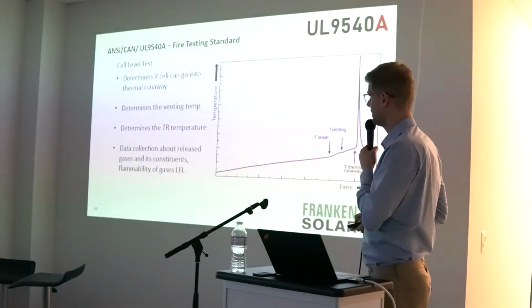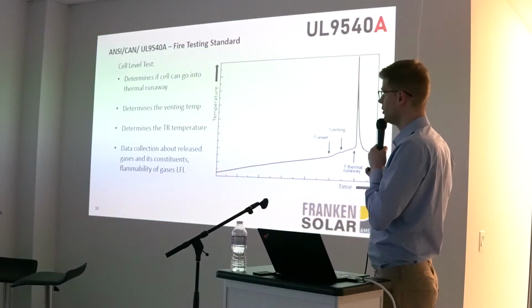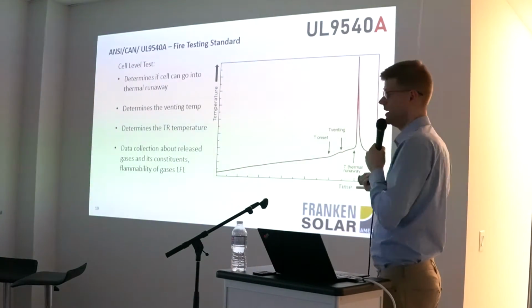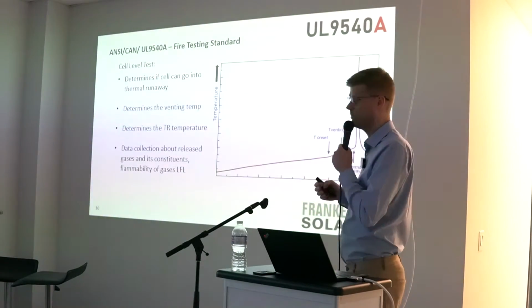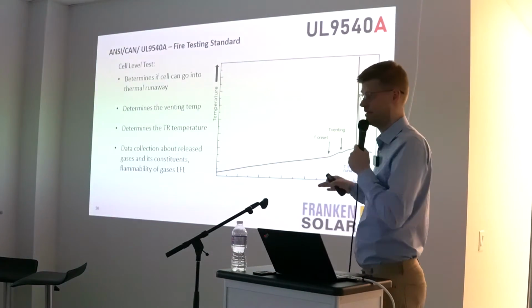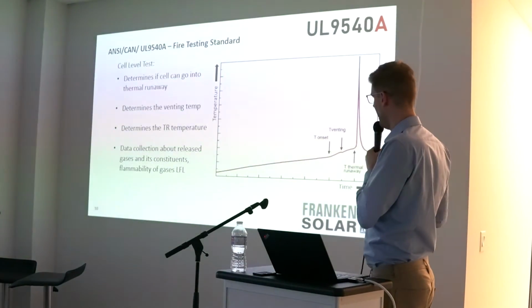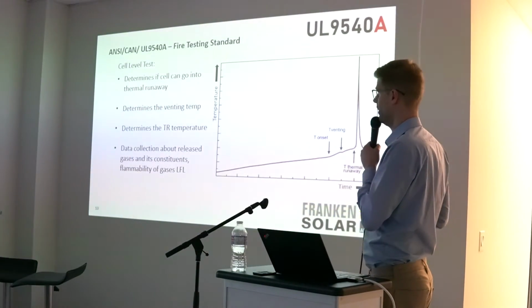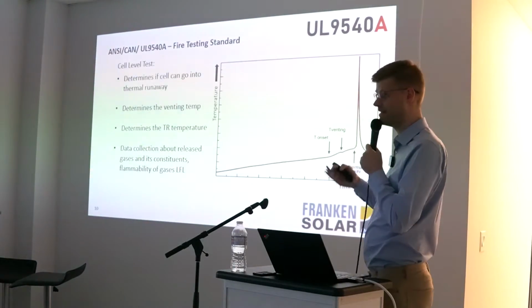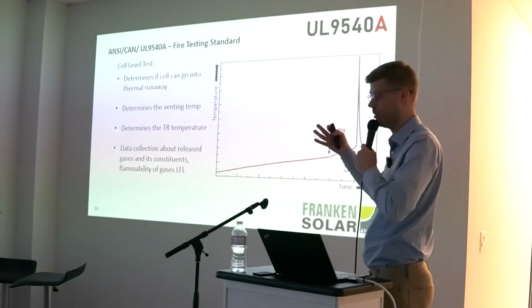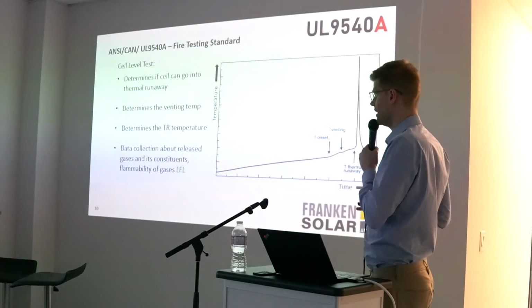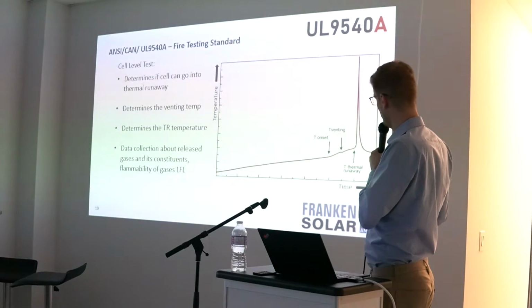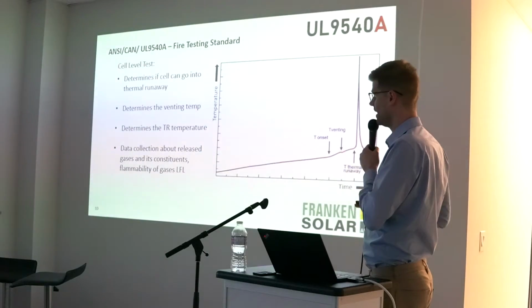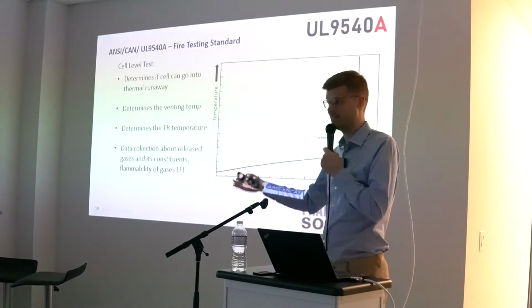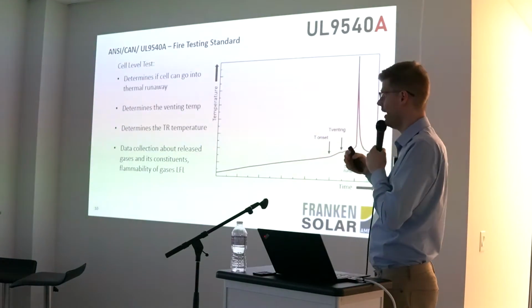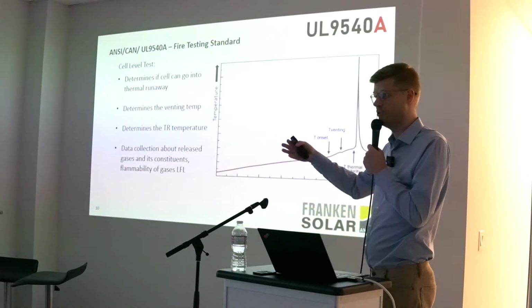Jumping right into the cell level here, the cell level test determines if there is a thermal runaway. The answer I already gave: there will be a thermal runaway with pretty much any commercially available cell in this market. Doesn't matter which manufacturer, doesn't matter where it's coming from, lithium ion has at one point a thermal runaway event. It also determines when the cell is venting, meaning just releasing extra pressure over a pressure valve that opens up to not explode.